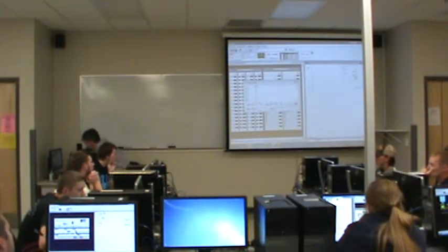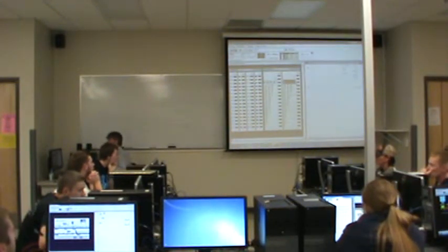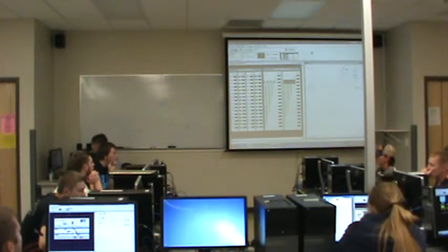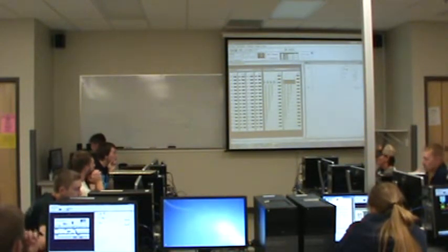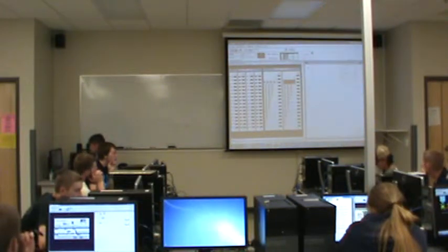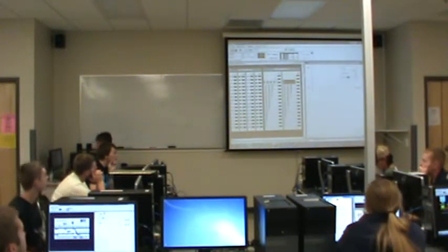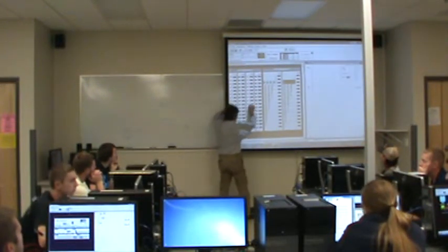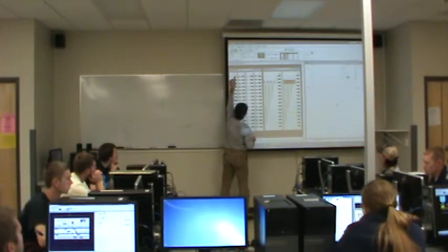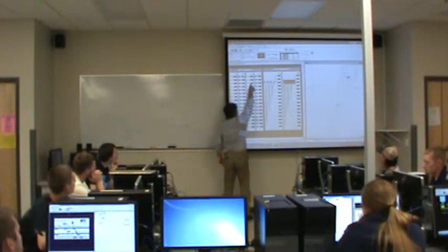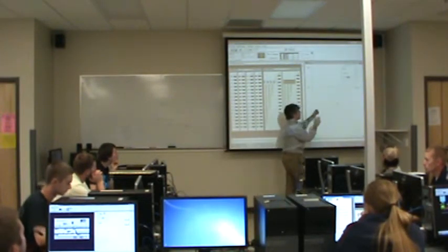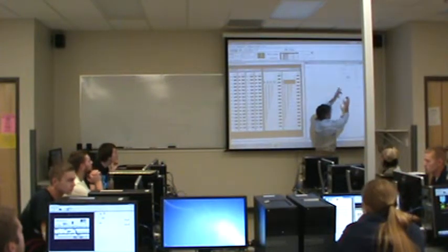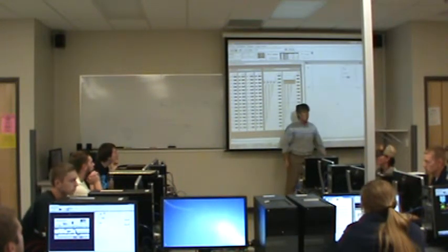Most of the time, you would add 2 words of data where you don't know what those words of data are going to be. So, for example, I might add the word of data at I:1 and the word at I:3. Now, what words of data would those be? Those would be these 2 words of data, because I'm referencing I:1, which is all of these bits, and I:3, which is all of these bits, and it'll interpret those 2 words as numbers, add them together, and put the result in memory at address 0.